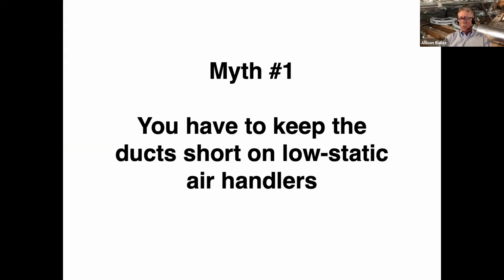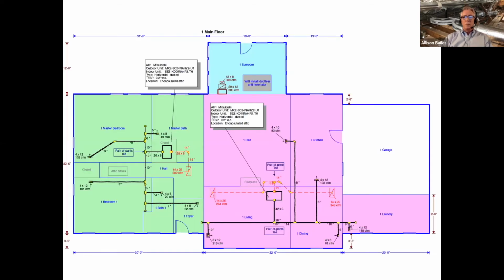All right, let's get into some of the real stuff here. So one of the things about low static air handlers that a lot of people believe, and this is common, I've had a lot of people say this: you can't put too much ductwork on a low static air handler because it just doesn't have the oomph to push that air through a long duct system. And that's not true. Here's the duct plan for my house.